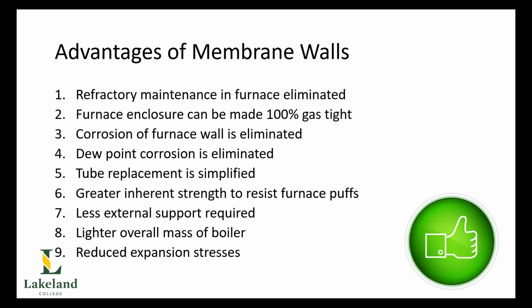Now, why do we go for these membrane walls or these water walls in modern boilers? Well, first of all, as I mentioned earlier, refractory maintenance is virtually eliminated. There still will be a little bit of refractory around the burner throat, but that's really about it. Secondly, of course, by having membrane walls that are gas tight, we can make our furnace enclosure completely gas tight, which means we can pressurize it. And again, that depends upon the type of draft of our boiler, whether it be forced draft, balanced draft, or induced draft.